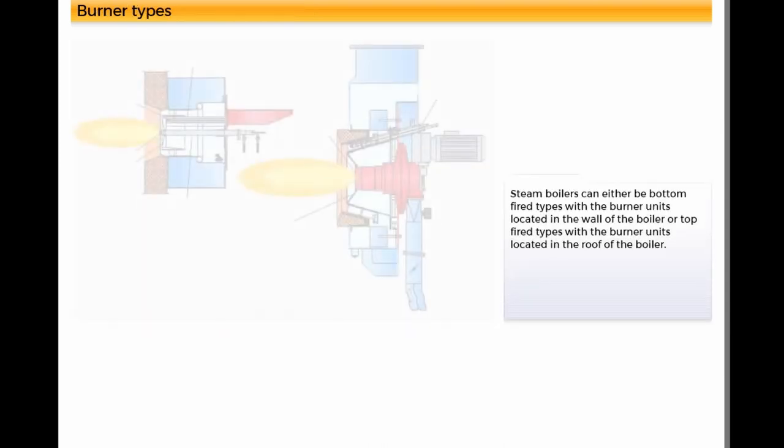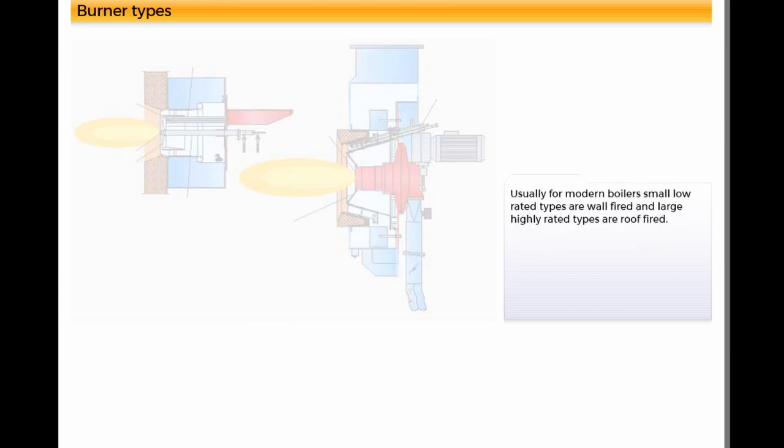Steam boilers can either be bottom fire types with the burner units located in the wall of the boiler or top fire types with the burner units located in the roof of the boiler. Usually for modern boilers, small low rated types are wall fired and large highly rated types are roof fired.